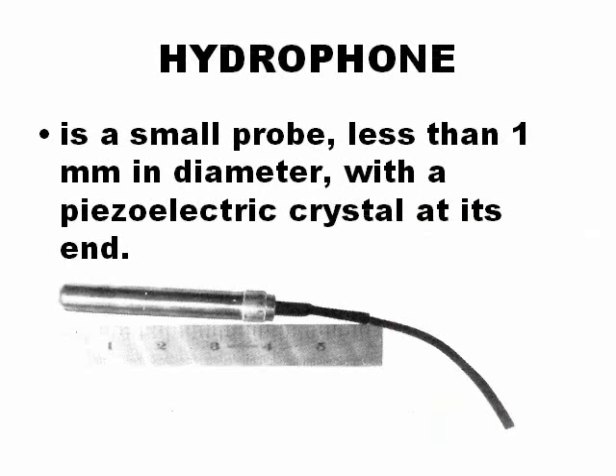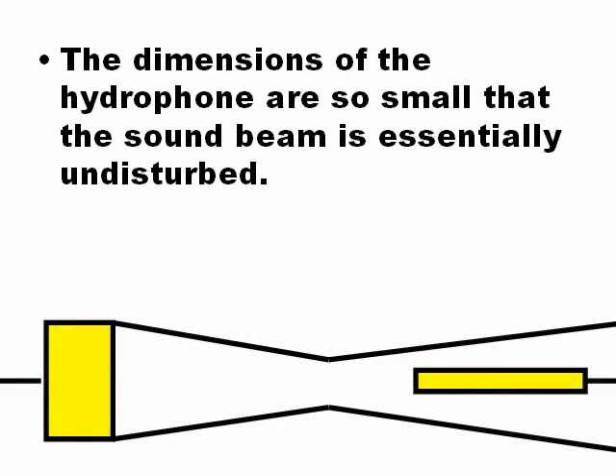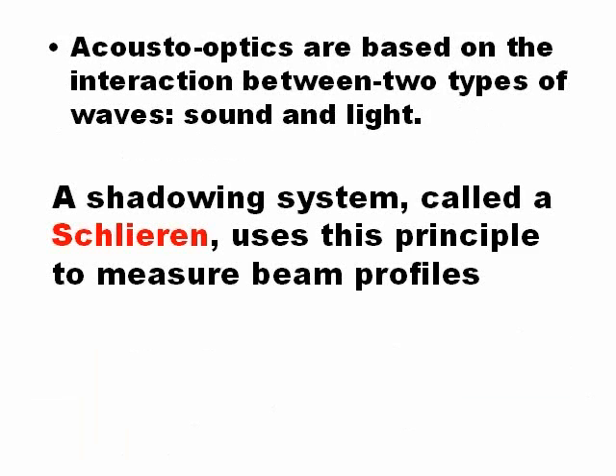A hydrophone is a little probe less than 1 millimeter in diameter with a piezoelectric crystal at its end. The dimensions of the hydrophone are so small that the sound beam is essentially undisturbed. Acousto-optics is based on the interaction between 2 types of waves, sound and light. A shadow system called Schlieren uses this principle to measure the beam profile.